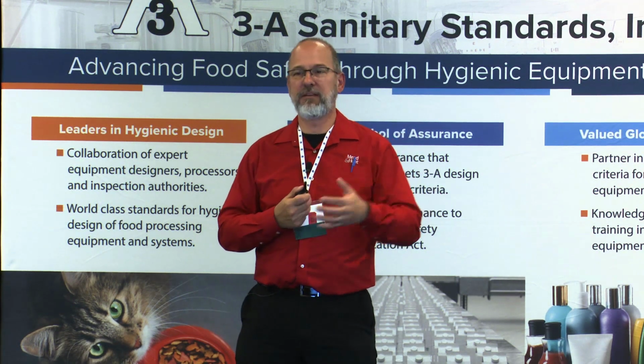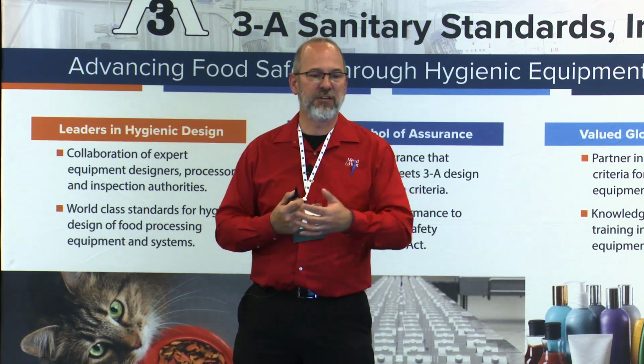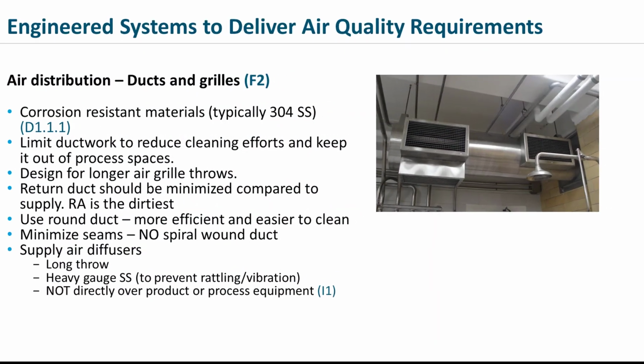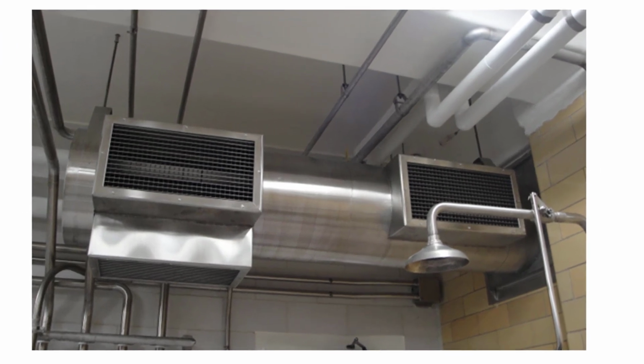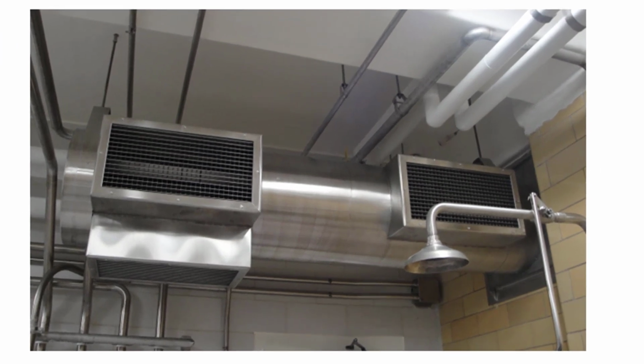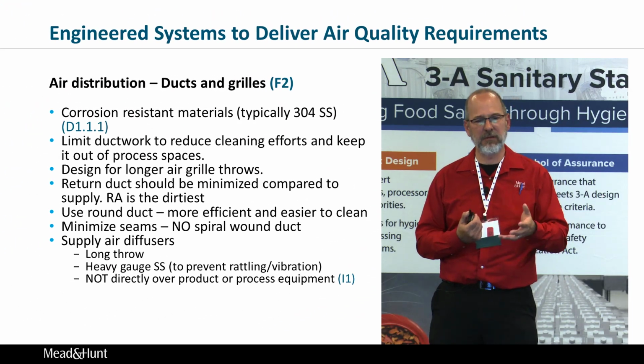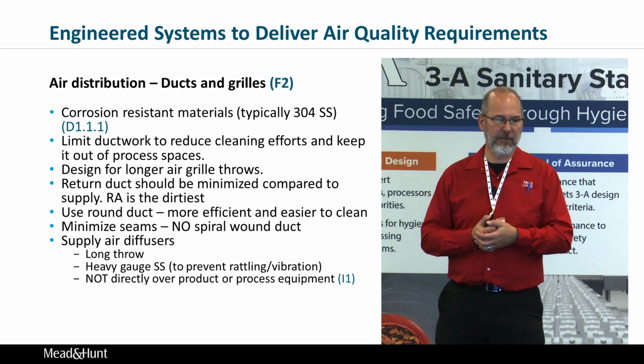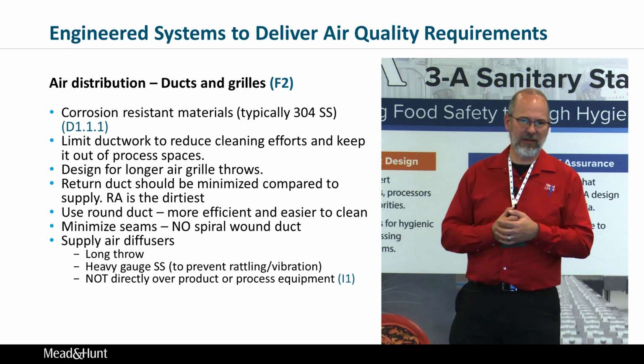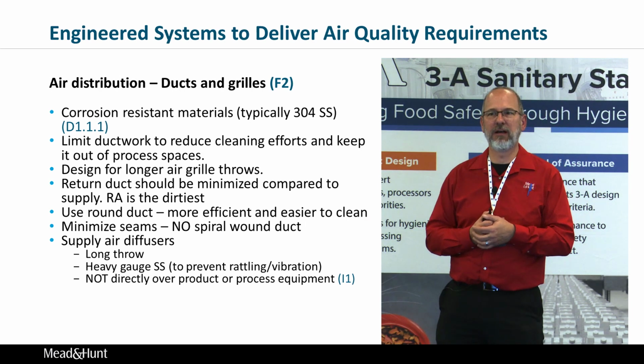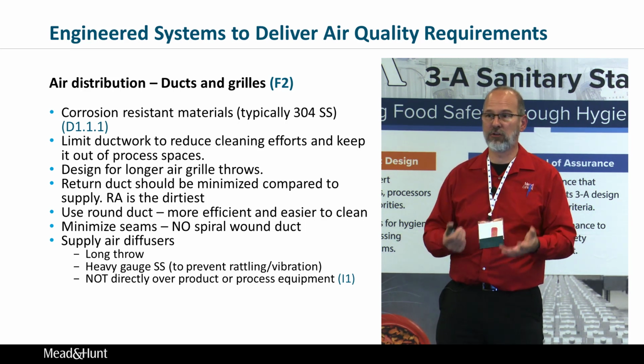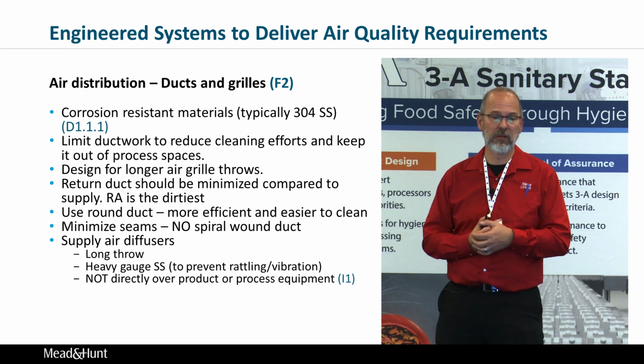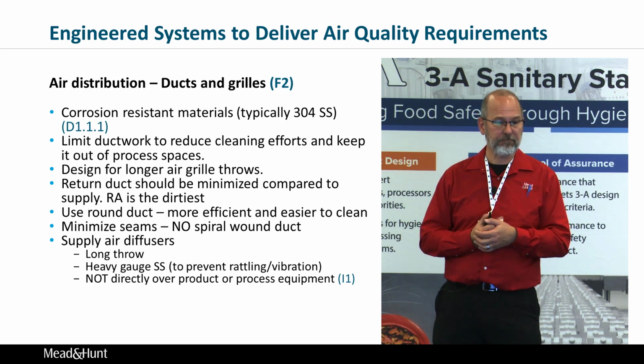So I talked about the air handlers a little bit. Distribution ductwork. You want to make your ductwork and air distribution components out of a corrosion-resistant material. Typically, it's 304 stainless steel, but there are some other materials out there. I've seen IMP paneling used for large ducts and things like that, but typically we see stainless. In general, as a designer, I like to keep the amount of ductwork I design and install to an absolute minimum, because the more you put in there, the more it costs, the more you have to clean. So the less you can put in, the better.